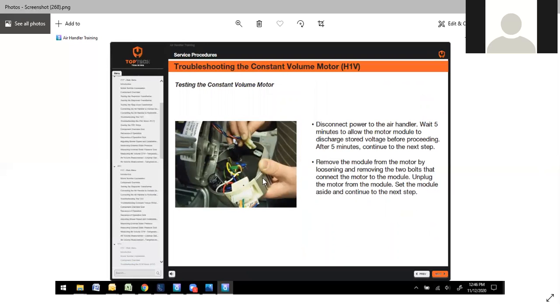Testing the motor, you can take the module off. 2 screws will hold that module off. You'll have a little retainer ring around here. Pop that off. Take your pin connector out of here. Then you'll actually remove the module. Set it to the side.